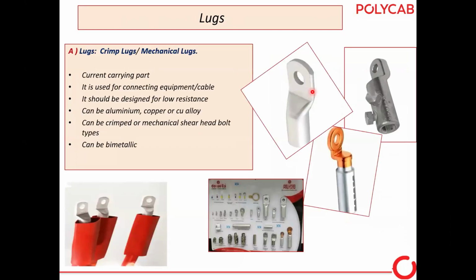Let's see lugs. Again, in the joint, the ferrule is the current carrying part. In the termination also, the lug is the current carrying part. Generally, people nowadays prefer bimetallic lugs or mechanical lugs, or if an aluminum conductor is there, aluminum lugs are used. It is connecting to equipment or cables. It should be designed for low resistance and can be aluminum, copper alloy, crimp or mechanical shear type, or both, and it can be bimetallic. Here I have shown the Dowells. Dowells is a Polycab subsidiary, and in Dowells we manufacture lugs, glands, all types of these. And this is the oldest company in India for the manufacturing of lugs and glands.